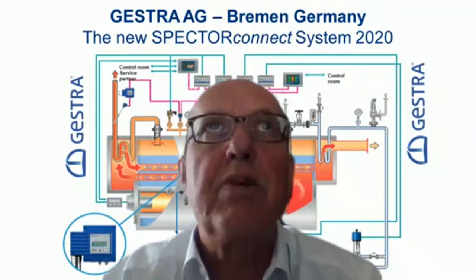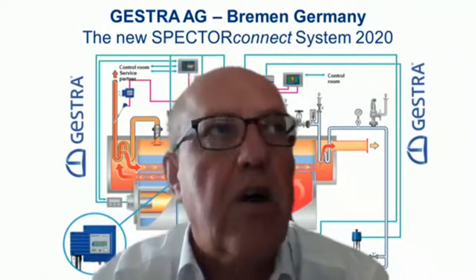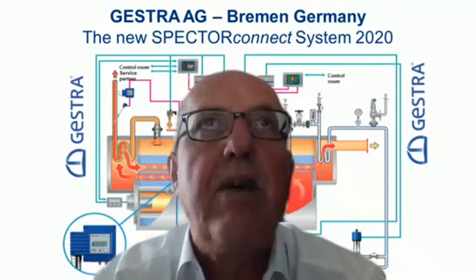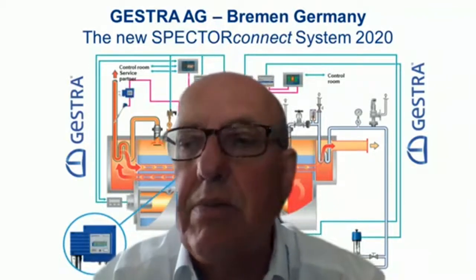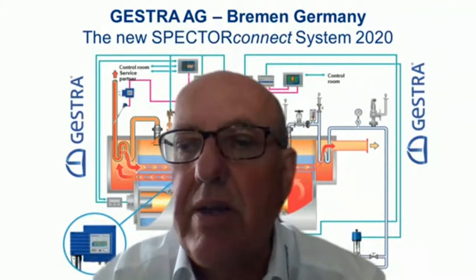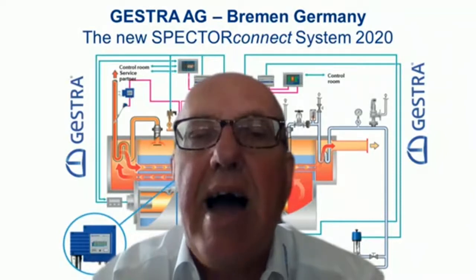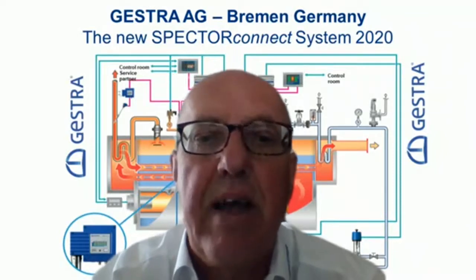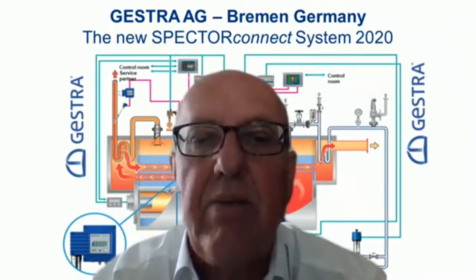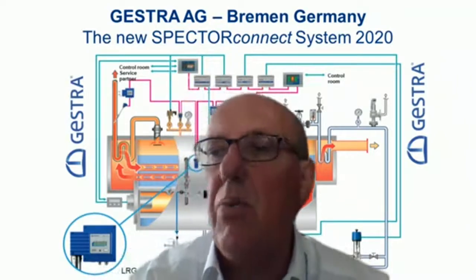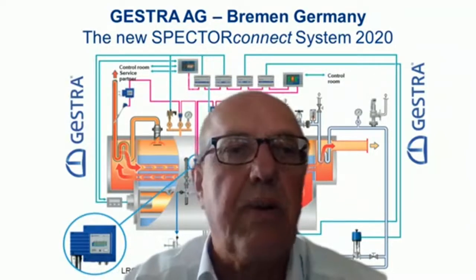It is not possible to say the steam trap has a leakage of 3.815 kilograms per hour. That is not possible with ultrasonic noise detection. But we can get a rough idea of the amount of condensate or steam loss with this system. That is what I want to answer to this question.